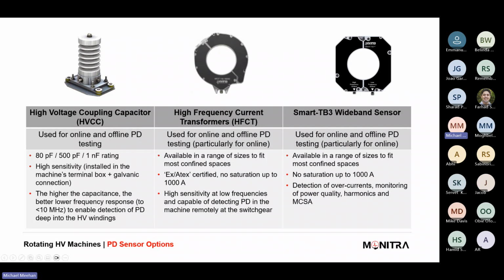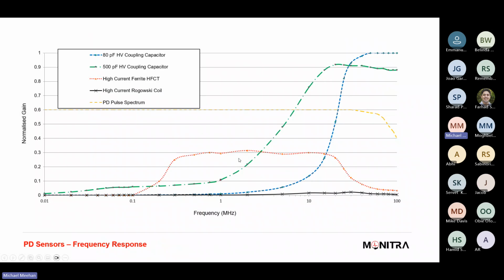And you can then also measure with the TB3 the operating frequency of the machine. If the machine's operating at, say, 30 hertz, then you can do your phase resolved pattern at 30 hertz, and you can still maintain that phase resolved analysis. Without the ability to detect the frequency of the VSD machine, you're just not able to do that PRPD analysis. Therefore, you can't do PRPD or PD analysis on a VSD machine. So that is quite a useful tool, and we do use that a lot in oil and gas, where there are a lot of VSD fed machines.